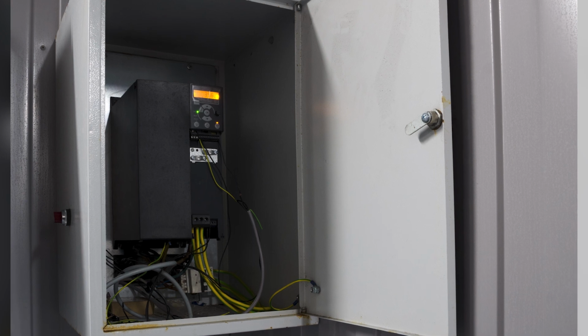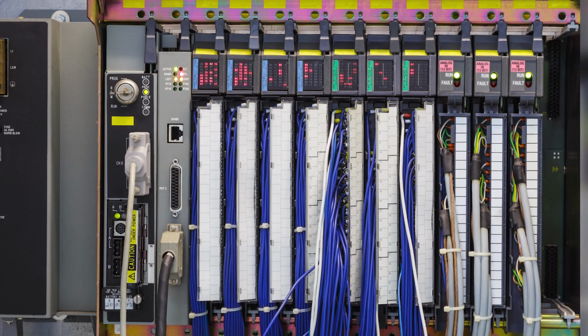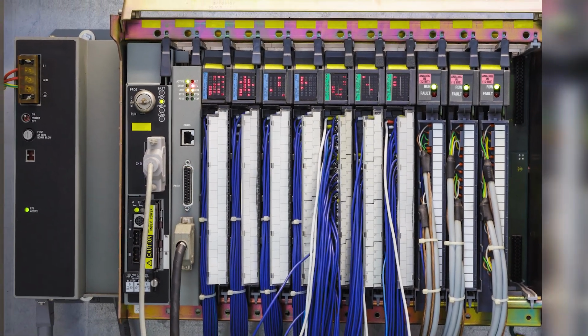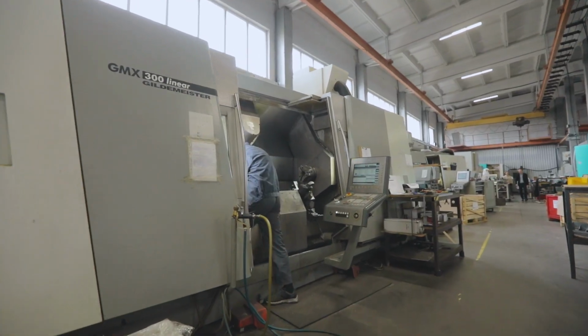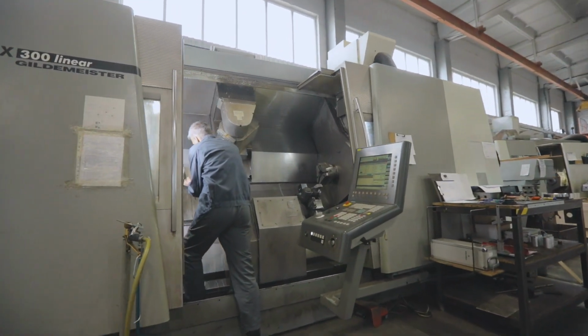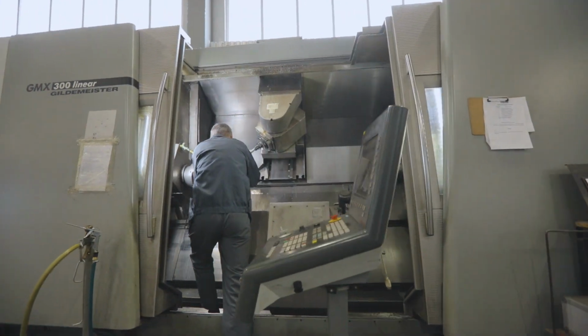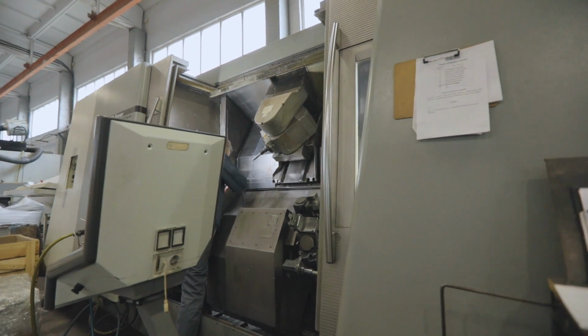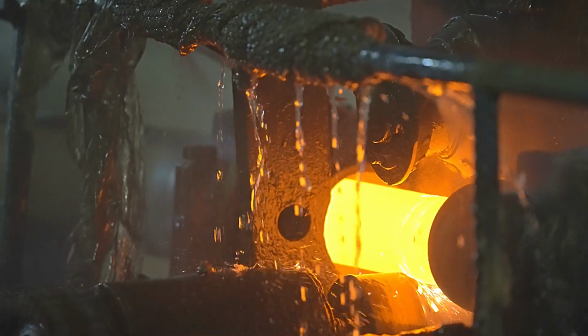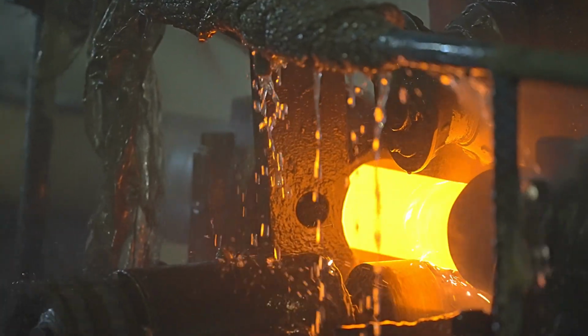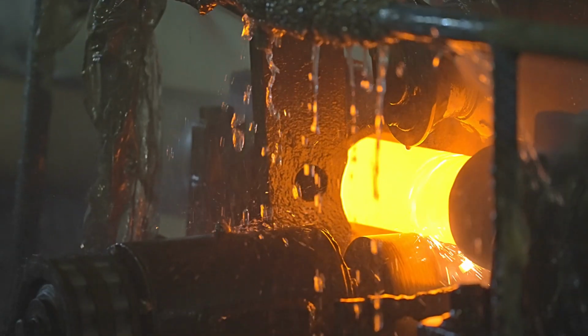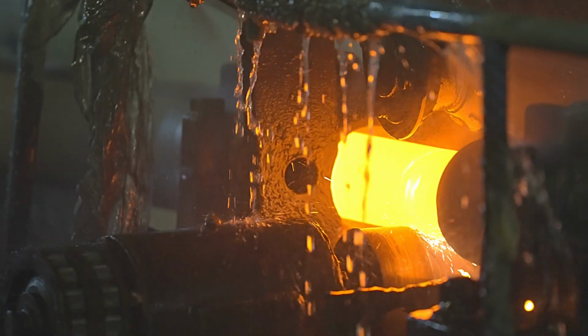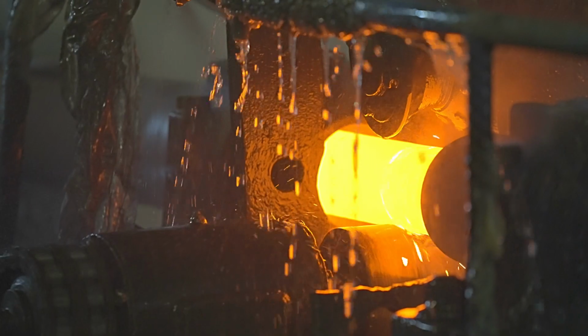Things like variable frequency drives, computers, PLCs, things like that. Industrially, UPSs are applied in many different applications. One is for anything that uses a PLC, CNC machines of all sorts, automatic transfer switches, and VFD controls. When the power goes out, those devices can typically shut down. Anything that's in process on the machines will typically be scrapped. The UPS will prevent that from happening.